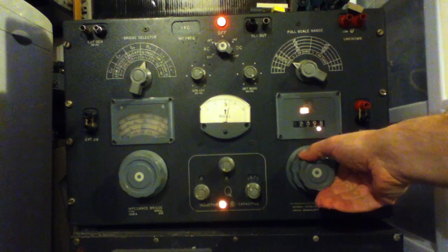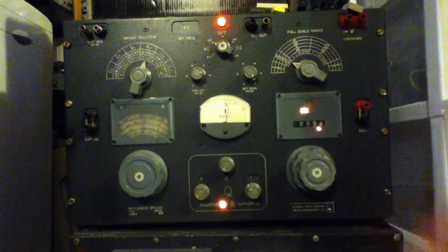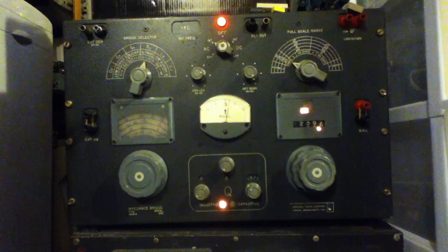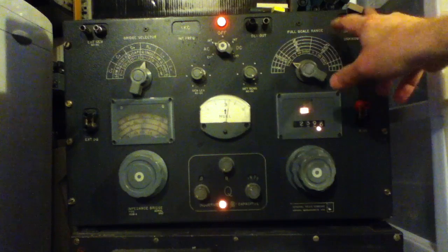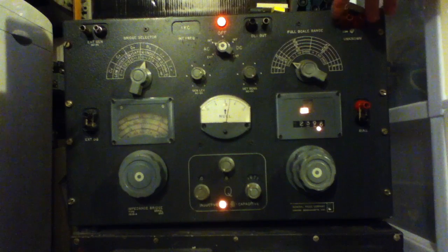So okay, we're homing in here on the null setting, and that's about it right there. So our reading is 239.6 milliohms. So there, try and do that with your DMM. That's nice and accurate. And one assumes it has 4-wire sensing internally, so whatever extra resistance we're seeing there is just whatever few milliohms that these binding posts have.